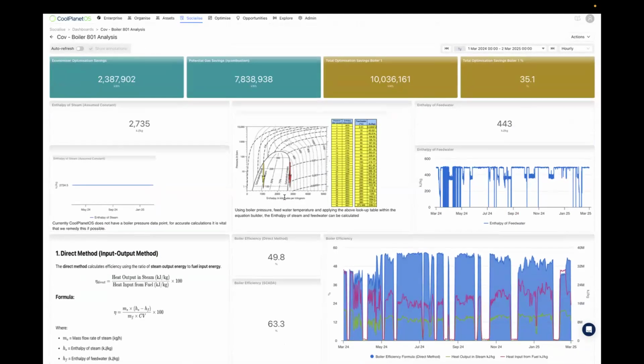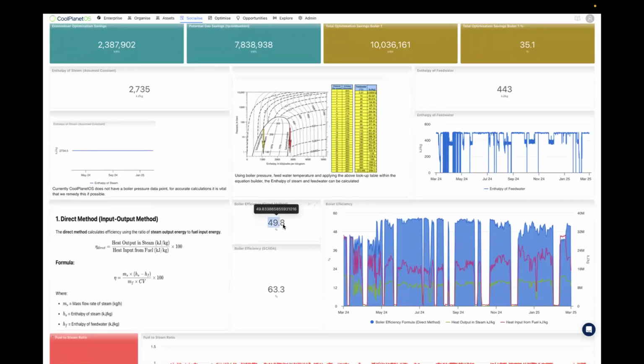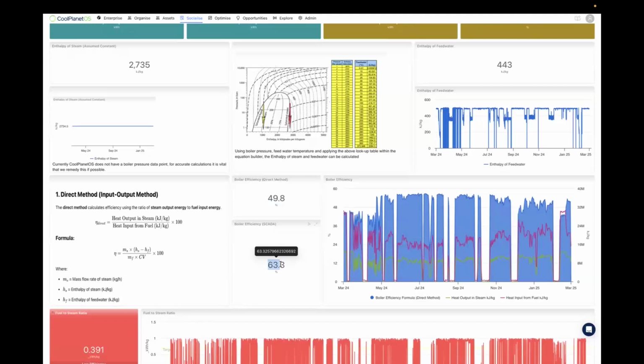So this next dashboard, this next feasibility slash analysis dashboard, is drilling down into one of those three boilers. And this was carried out on all three. So we're generating outputs, calculations around boiler efficiency. We're comparing it to what the SCADA system is saying on this particular site. And this boiler controller would have been programmed by the suppliers of this particular boiler. We're not quite sure how they calculated the boiler efficiency. So it's always good to double check and validate that efficiency output that you're seeing on screen.